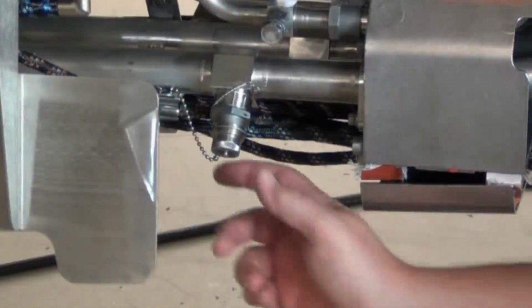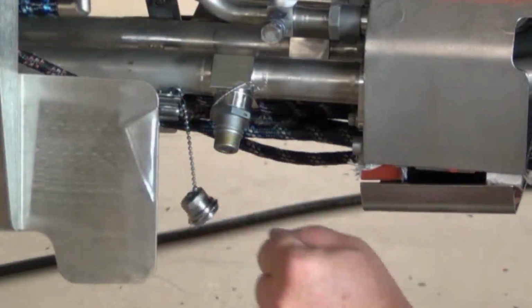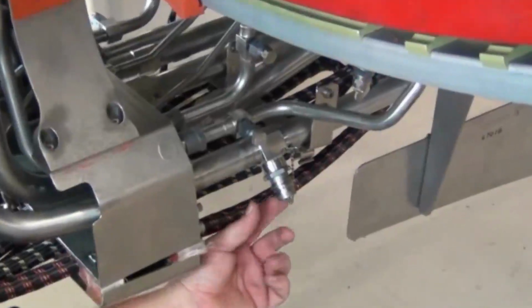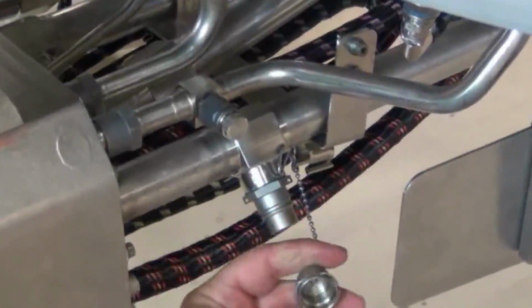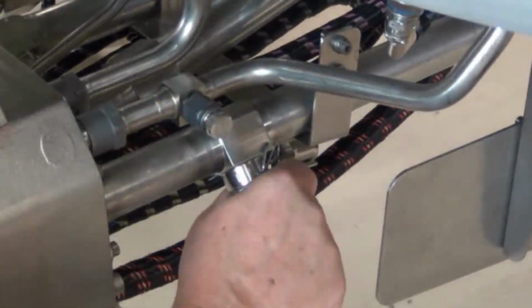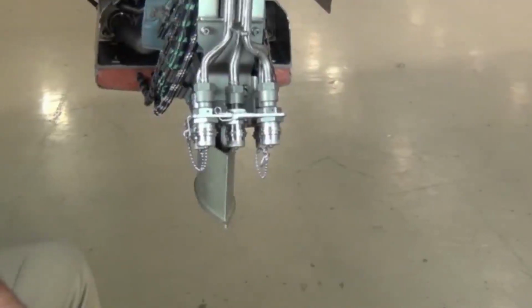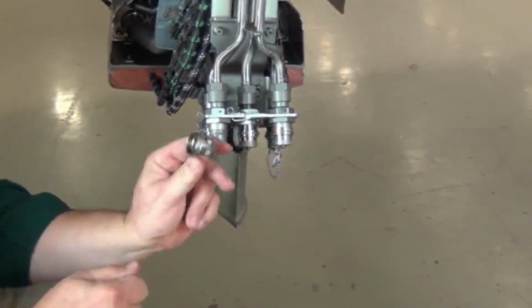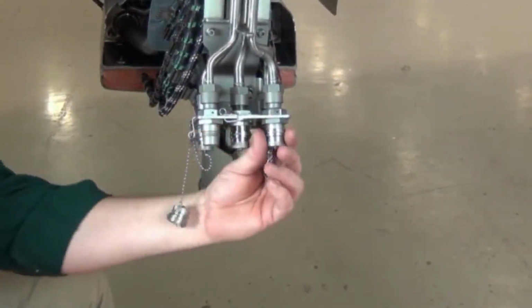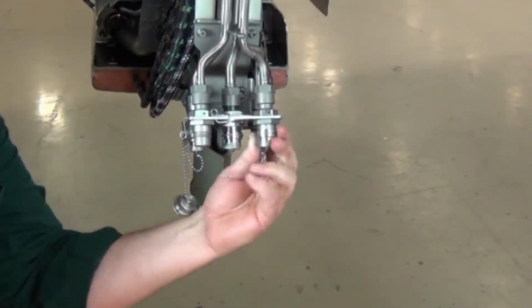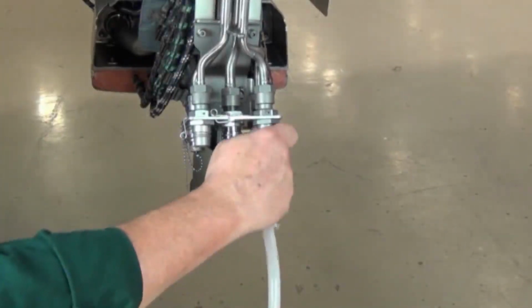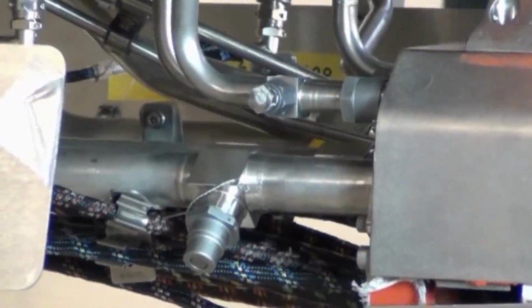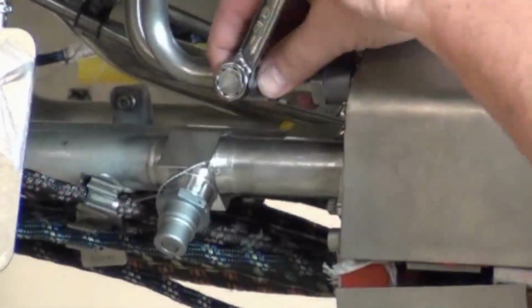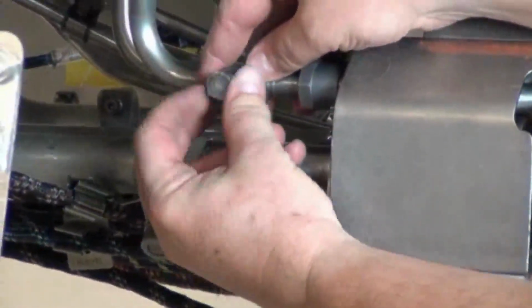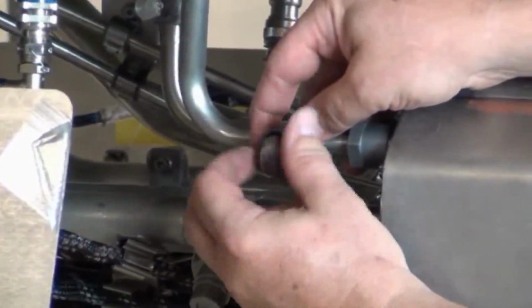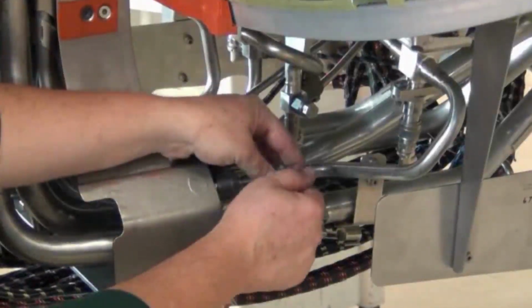One at a time, remove the drain plugs or caps of the engine oil supply line, oil return line, air oil heat exchanger supply line, and air oil heat exchanger oil return line, and drain the engine oil into a container. Relieve the pressure in each of the VFSG systems by removing the caps and attaching the overfill line of a remote service cart to each of the VFSG's overfill drain valves. Drain the left and right VFSG oil systems by removing the plugs of the VFSG's air oil heat exchanger oil supply and return lines, and draining the oils into a container.